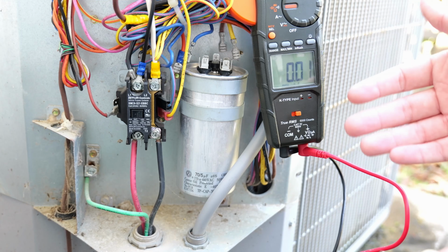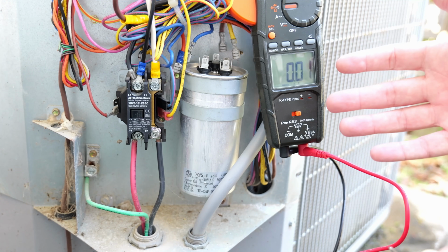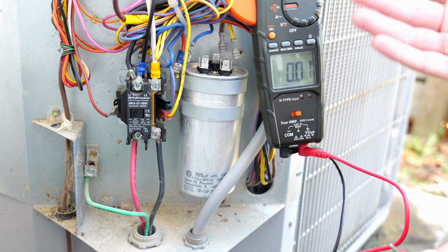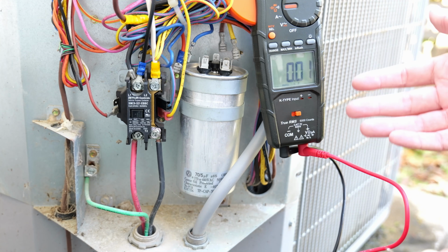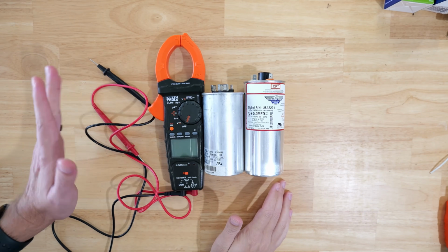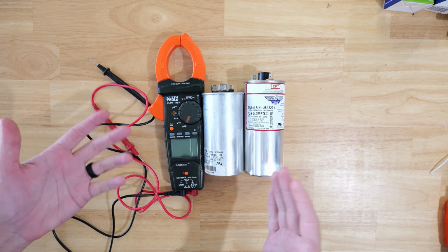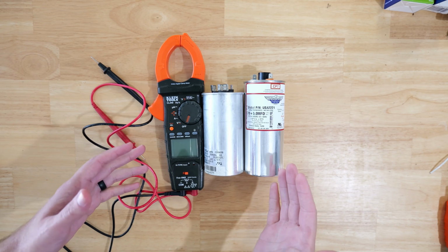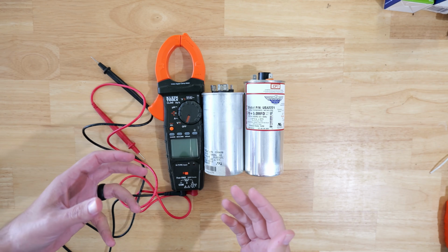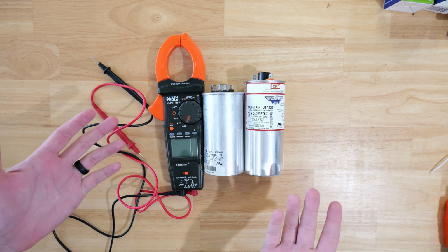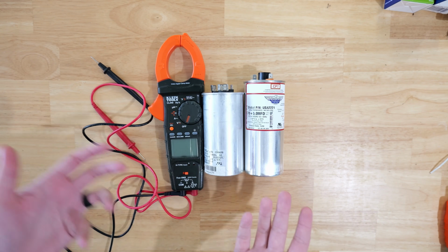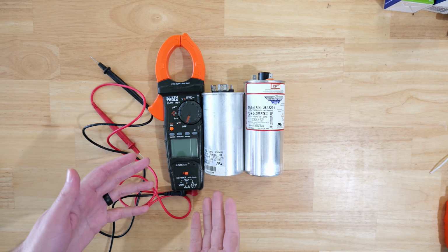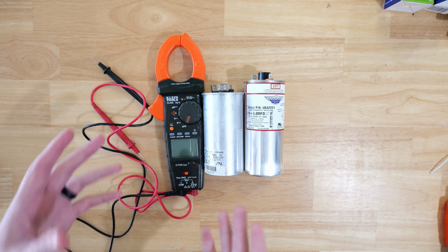But now I'm just going to really quickly show you up close what it would look like if you were testing a bad capacitor and what type of readings you might get. All right, so while the capacitor that's out in my AC unit is still good, which is a good thing, I want to really quickly demonstrate for you exactly what it looks like when you test a bad capacitor, what kind of readings you might expect if your capacitor is actually bad, and just how clear it really is.